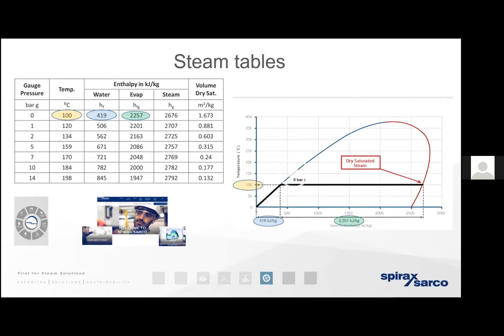The term 'dry saturated steam' — the saturated part means the steam is saturated with energy; it physically cannot contain any more. The maximum energy steam can contain at zero bar gauge is 2,676 kilojoules. But the term 'dry' is critically important. If we're distributing wet steam leaving the boiler through hundreds of metres of steel pipework, more and more of that steam will condense out, giving up energy to the pipework — a significant heat loss representing significant inefficiency.